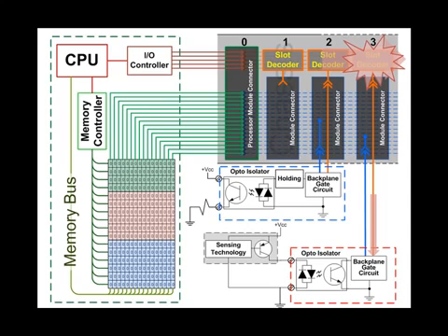Logically, since the processor knows which slot it activated, it knows which word in memory to gate the 16 states from the backplane into that word in memory. So the memory controller activates a word, and the information from those 16 bits is then stored in that word. The input image from the input module in slot 3 is now stored in memory variable I:3.0 for use by the program logic in the next step of the sequence.